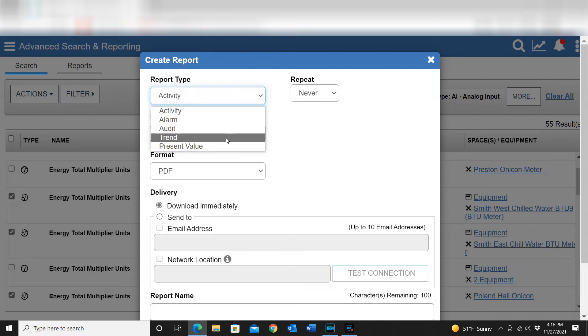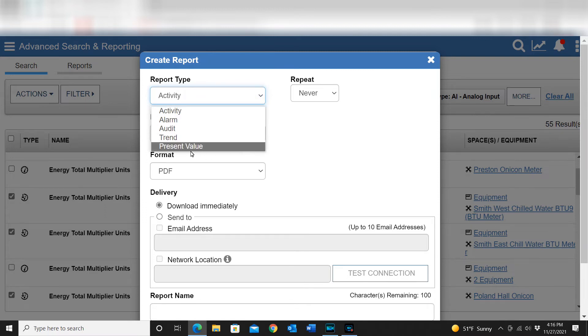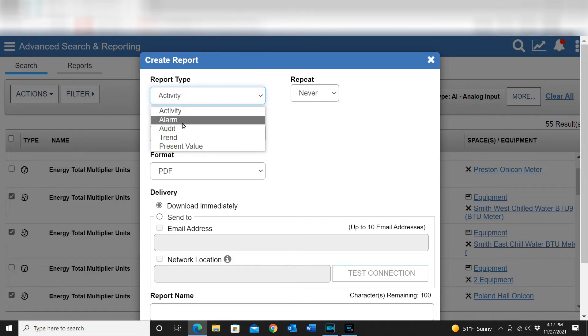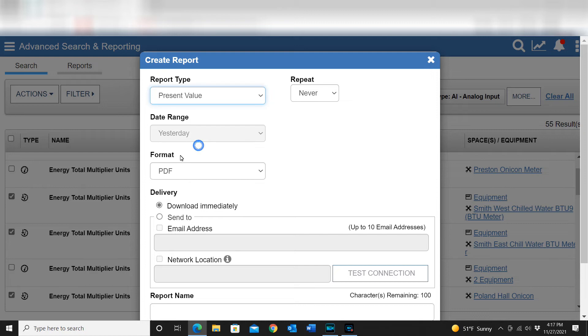I can set the report type. If you want the present value of something you select that here. If you want trend history, that depends heavily on how your trends are configured — you need to make sure your trends are set up to record data for the time period you want, otherwise that information will roll off and won't be available for the report. You can also do alarms or audits; there's a lot of options. I'll select Present Value.